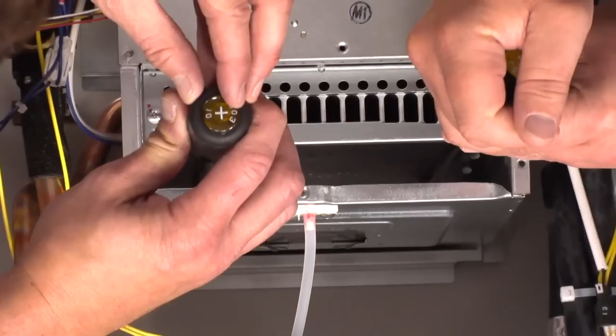I'll see if I can, there. You see those two screws? We're going to take those out. And when we're putting this back together, we've got to remember to put those back in too. That's something people always forget sometimes. Jerry, a service tip while we're doing this, that air damper that you mentioned that we don't have to take those screws out, if for any reason we ever had to replace the burner, the new burner won't come with that damper, so we need to make sure we move this from the old burner to the new one. Good tip.